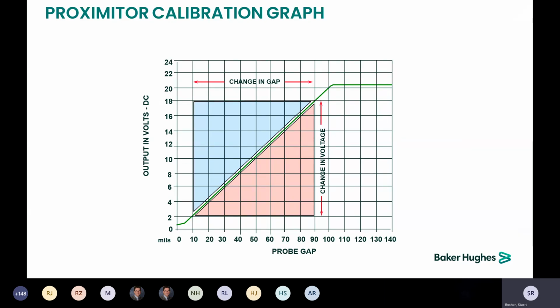The target does need to match the material of the shaft. Then you have a meter connected to the Proximitor looking at the gap voltage, or the DC voltage, and you record that as you roll the spindle micrometer out. Every 10 mils, you will record the gap voltage.